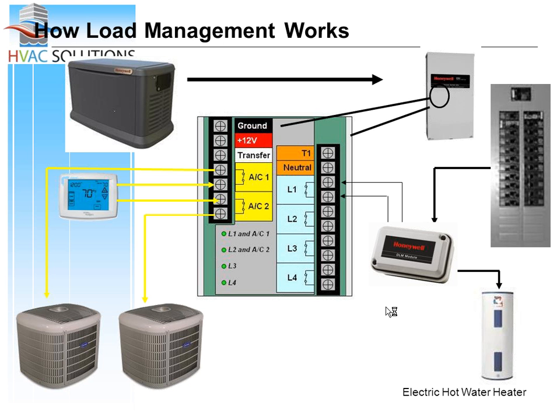So you need this DLM module, which is basically a 50-amp contactor, to turn on or shut off large 240-volt loads in a house. What is a large 240-volt load? Well, it could be an electric hot water heater, a well pump, an electric dryer, maybe a range. So those are the types of things that we're looking to possibly shed.